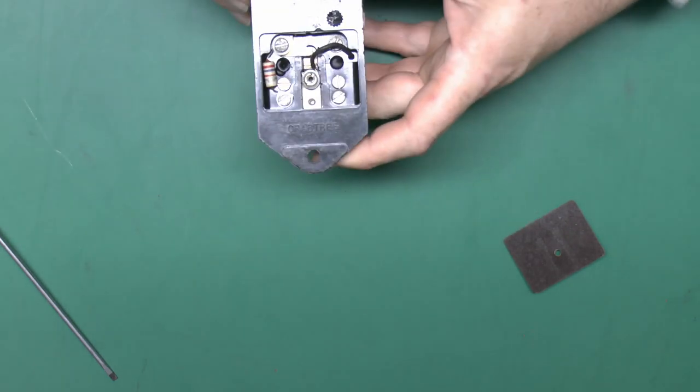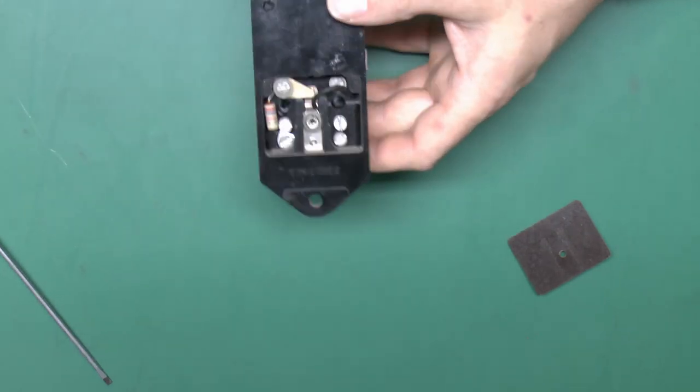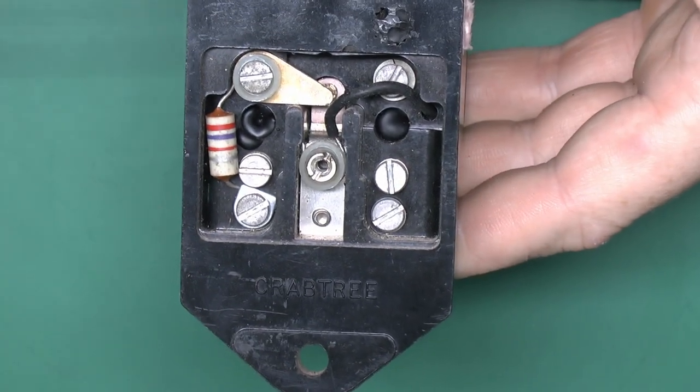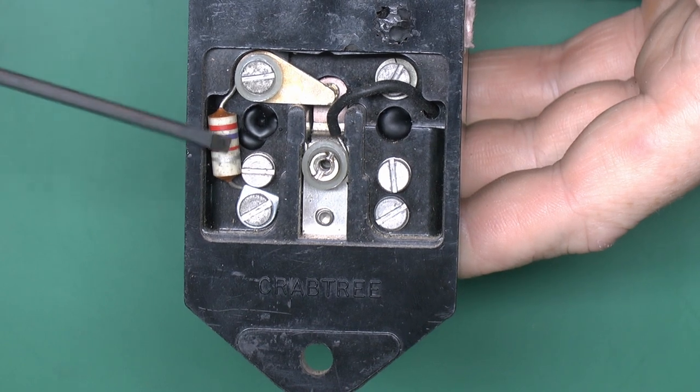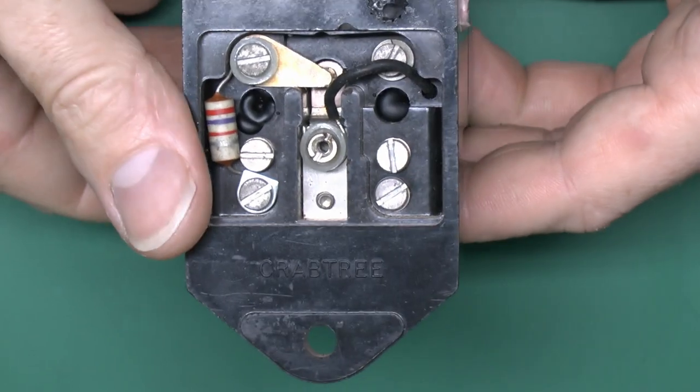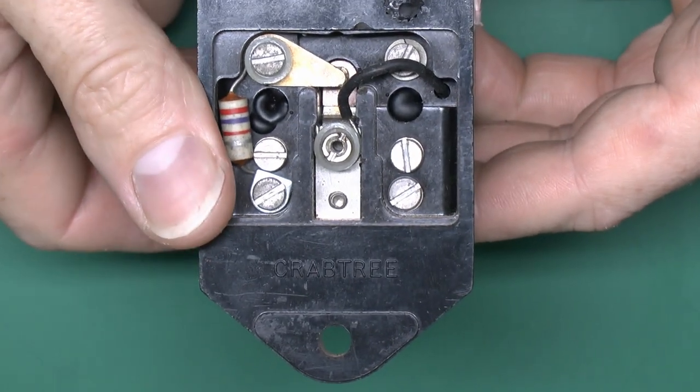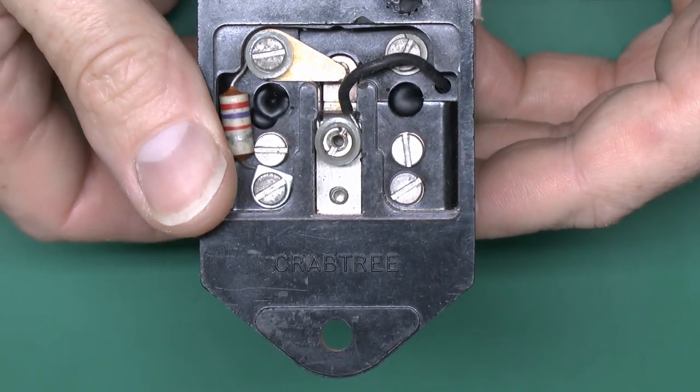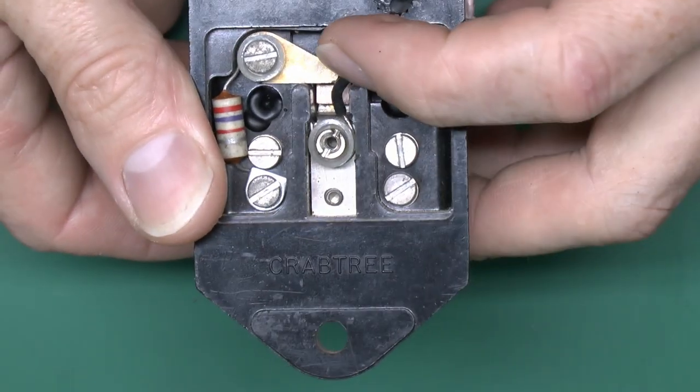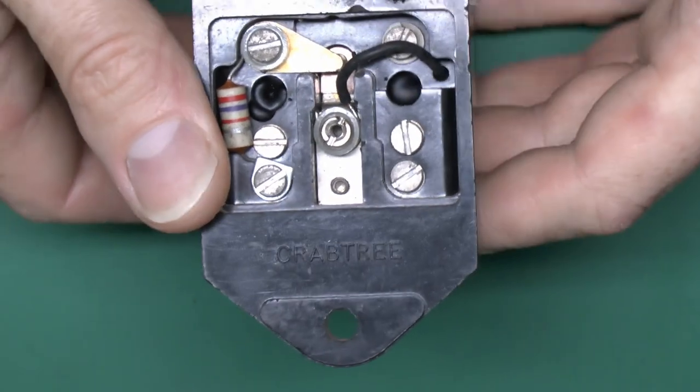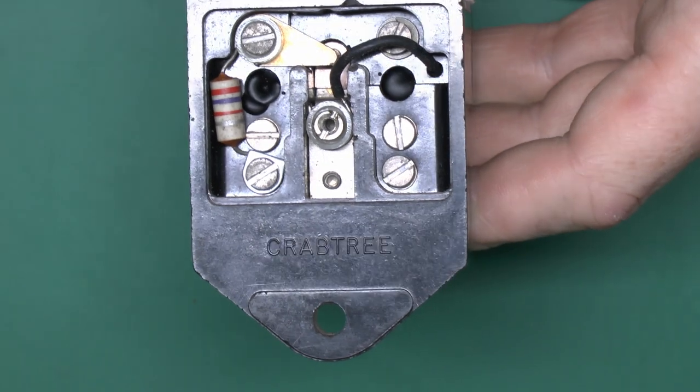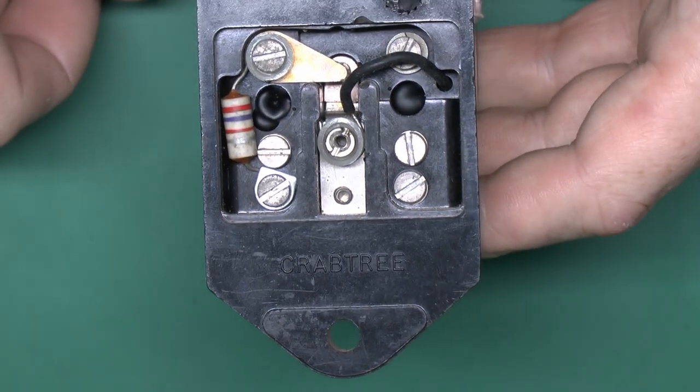Right, okay, so in here we've got the test resistor, which will obviously connect via the test switch. If we press the test button, we can see that part just moving in the bottom there, disconnecting at the bottom, and then reconnecting onto this top terminal, which goes via the test resistor and puts the line voltage across the coil, therefore hopefully tripping the device out.